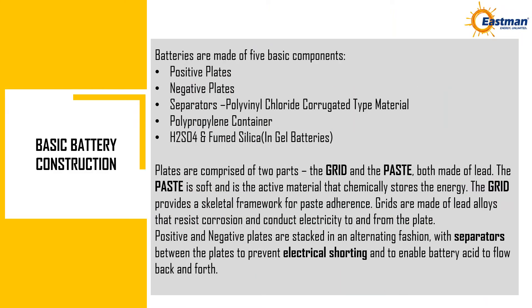Basic battery construction. Batteries are made of five basic components: positive plates, negative plates, separators of polyvinyl chloride corrugated type material, a polypropylene container, and sulfuric acid with fumed silica in gel batteries. Plates are comprised of two parts — the grid and the paste — both made of lead. The paste is soft and is the active material that chemically stores the energy. The grid provides a skeletal framework for paste adherence. Grids are made of lead alloys that resist corrosion and conduct electricity to and from the plate.